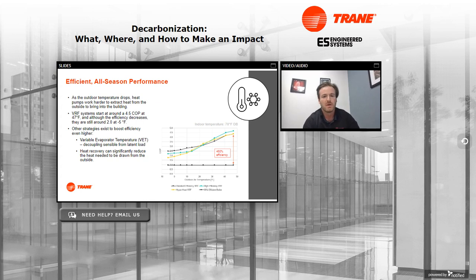Now you do start to lose some efficiency as you go down the line and it gets cooler outside because there is less heat. So you're going to need to work harder with your compressor to draw it. But at the end of the day, even once you're getting below 0, you're still at a COP of around 2. So you're still being twice as efficient with your VRF system as you would be using natural gas or electric resistance heating.